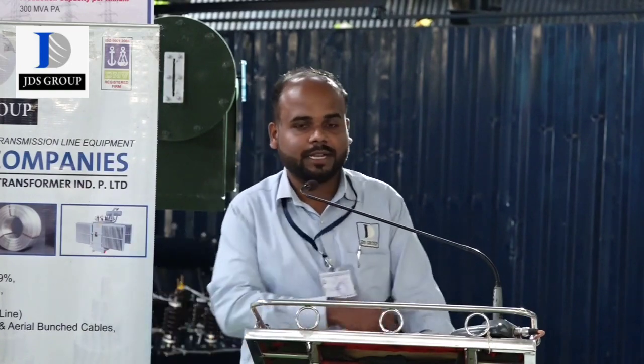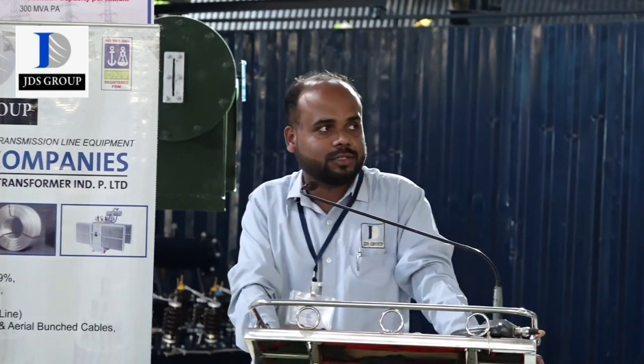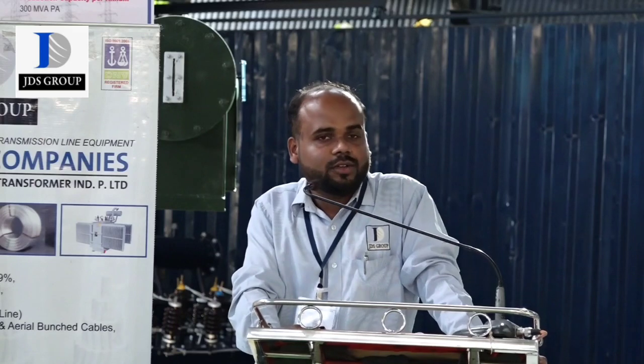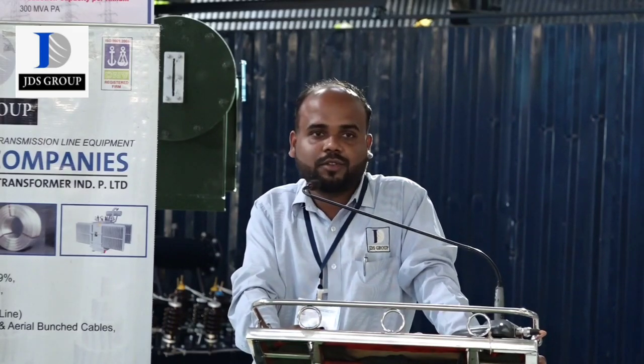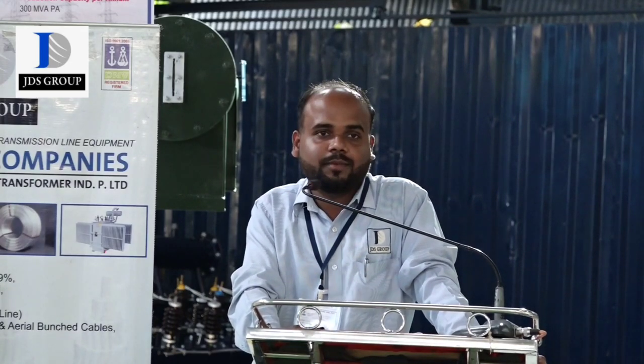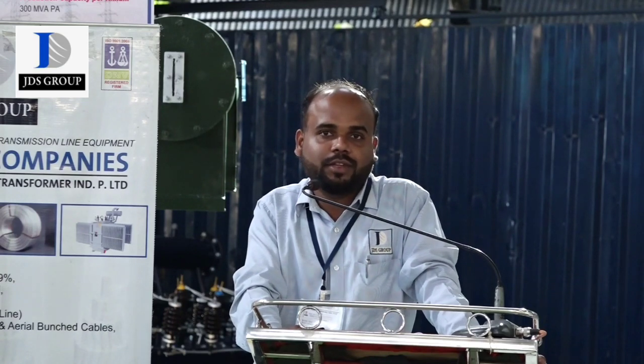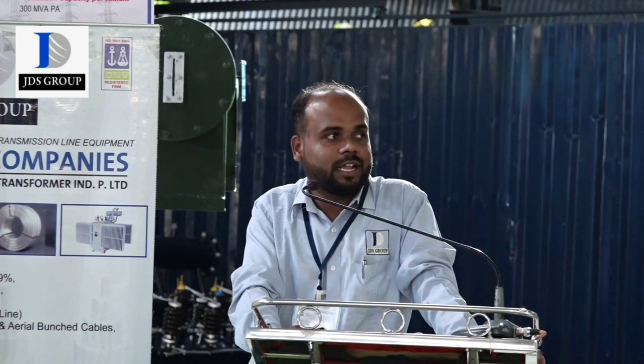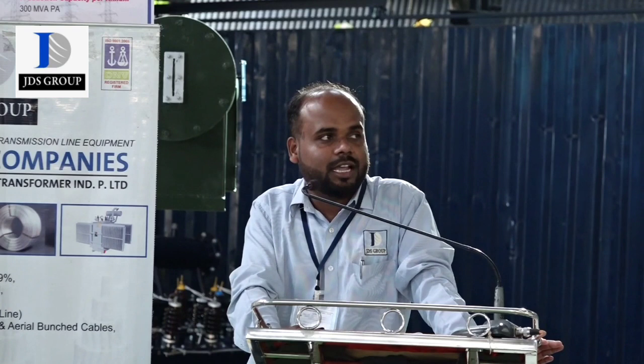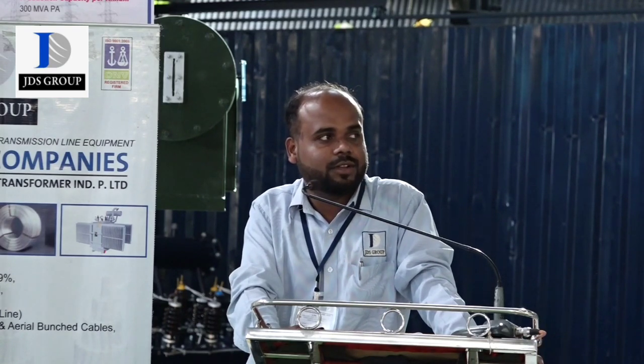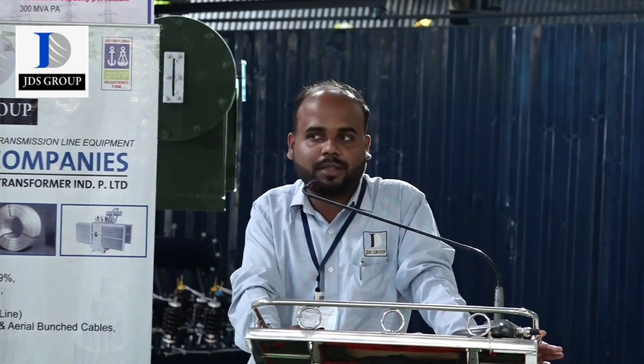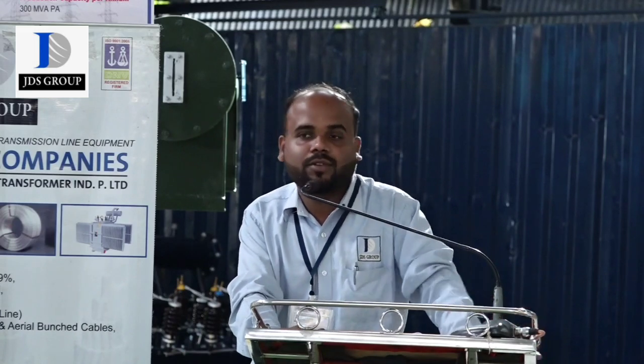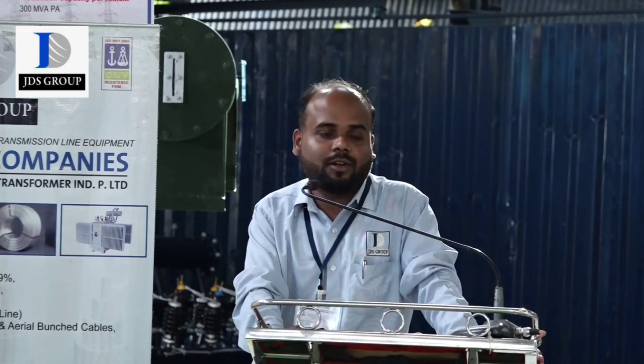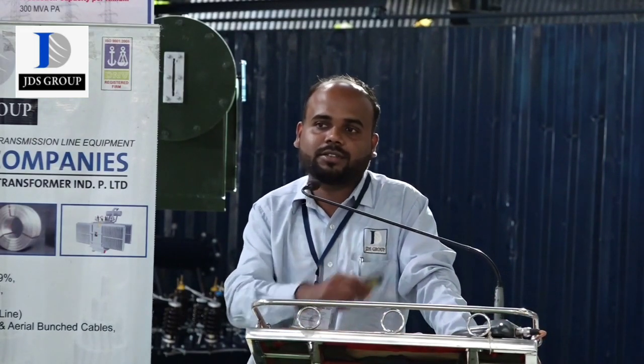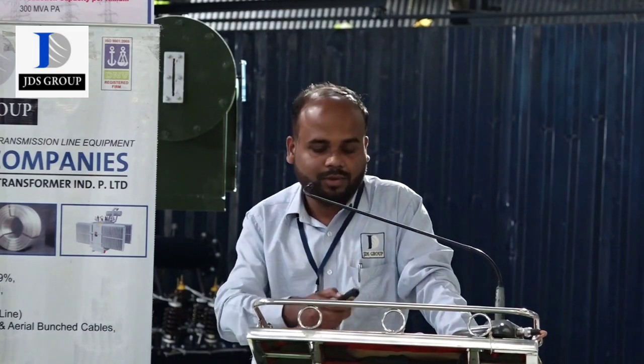After the voltage ratio, the next test conducted is the core loss, which is also the no load loss. The no load loss mainly tells the losses of the core. In this case, we provide the rated voltage on the LV side of the transformer. Our LV side voltage is 433 volts, and the HV side is left open. By using this, we know the quality of the core we are using and what losses we are getting from the core.